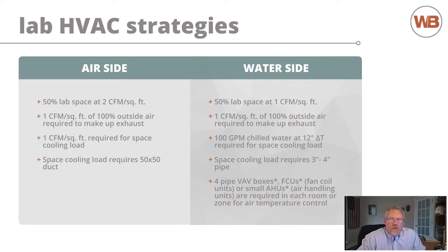For 30,000 square feet, you're going to need 100 GPM of chilled water. And again, you can change your delta T, but just nominally say it's 100 GPM. So in terms of space comparison, for air, you need a 50 by 50 duct. For water, to get that energy up and down through the building, you need a 3 to 4 inch pipe. Pretty significant difference.